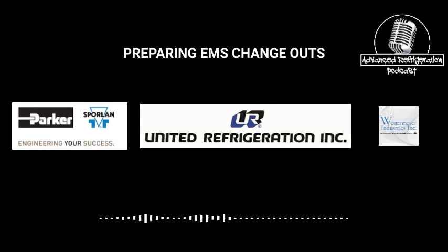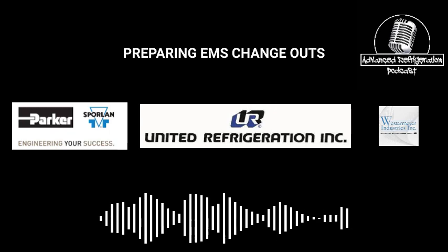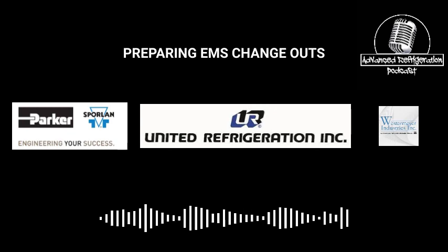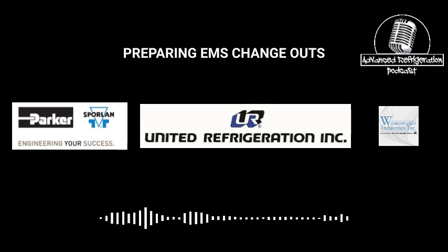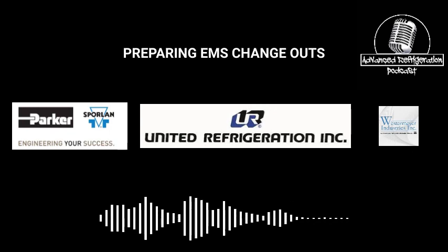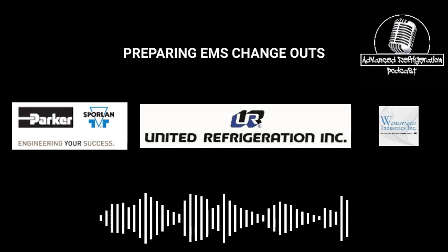And with Danfoss, if you don't hit everything, everything will be in a row. So like say if you had air handler 1, 2, and 3, and then rooftop 1, 2, 3, 4, 5, and 6. Okay, well, say there was another air handler that was added that you didn't know about, you had to add it. Well, now you can't make it air handler 4. You have to delete the first rooftop and make that air handler 4, and then redo the whole program from there on down. I don't have a ton of Danfoss experience, and I just had this happen to me, and it cost me like 6 hours of moving board points and naming. And yeah, do I think it's stupid? Extremely, but it took me a long time to make it look good because it was all unorganized.